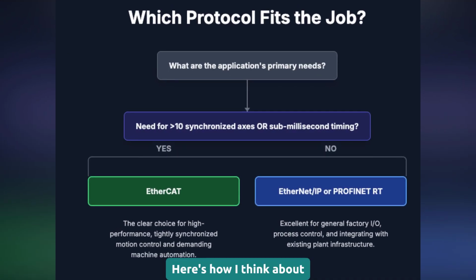Here's how I think about it. Ethernet IP for standard discrete automation, PROFINET for Siemens ecosystems, and EtherCAT when you need the absolute fastest timing and tightest synchronization. Each has its place. If you're doing basic I/O with cycle times above 5 milliseconds, Ethernet IP is probably fine, and you'll have more device choices. But if you're synchronizing 10 plus axes or need sub-millisecond timing, that's where EtherCAT's architecture really pays off.